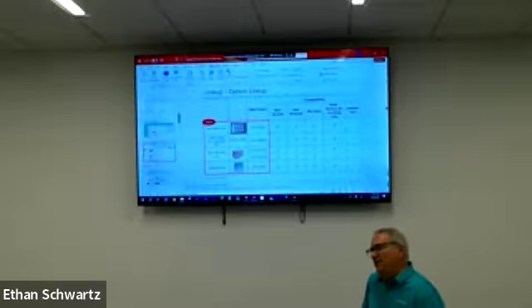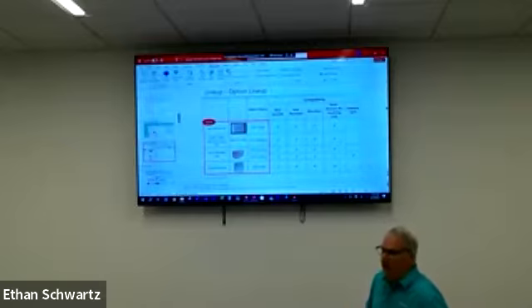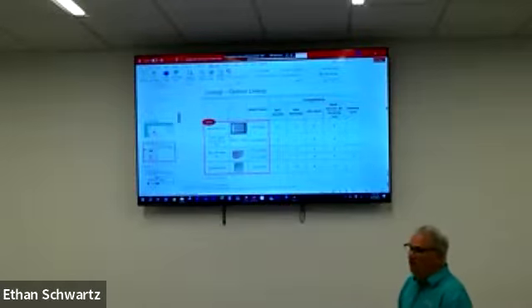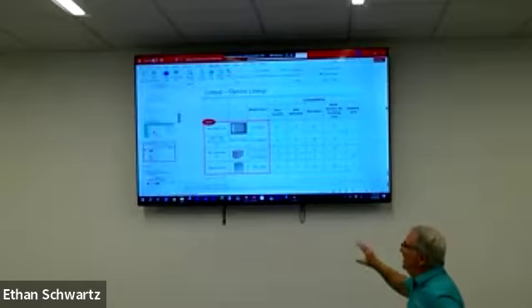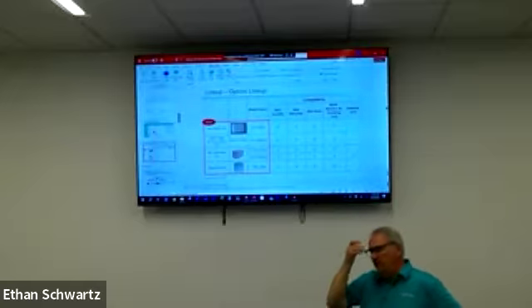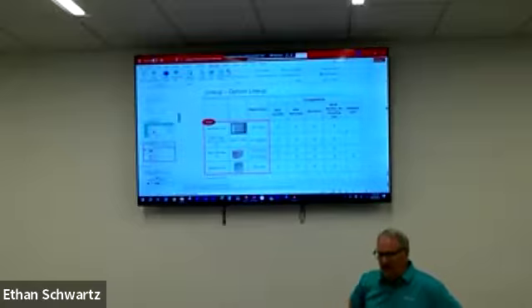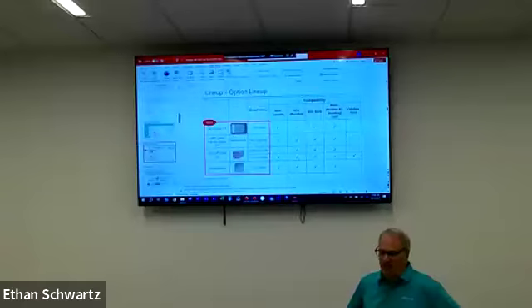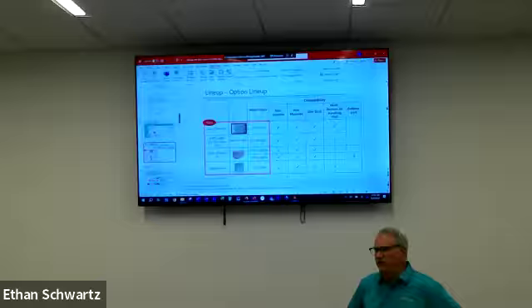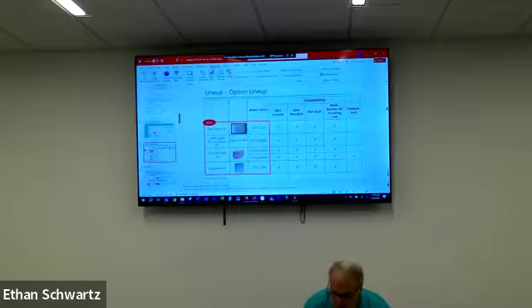And that's where knowing about the ERV or knowing about air circulation comes in. You guys aren't going to be doing ductwork, but duct work volume in an R32 calculation comes into play, and you get credit for that. It is a whole involved thing. I deal more on the VRF side, but I could see the gears working in your head, wondering how you're going to apply R32 to multi-zones and what that's going to look like. So I'll dig a little bit more and see if I've got some information for you on that, because our design simulator software.